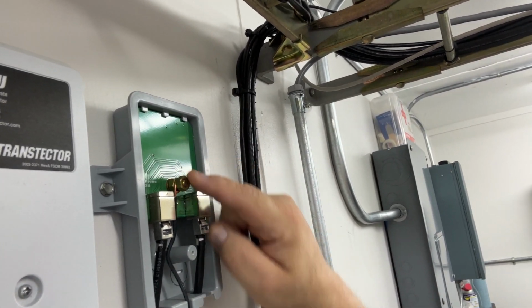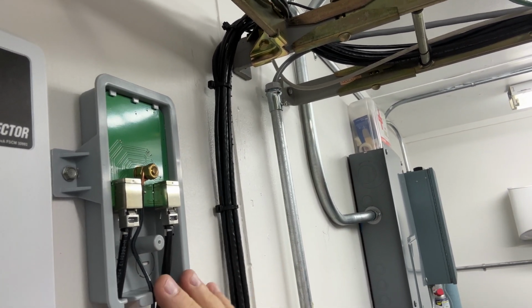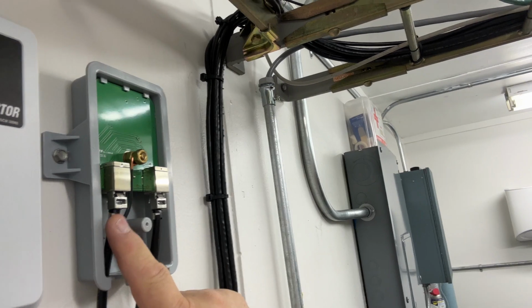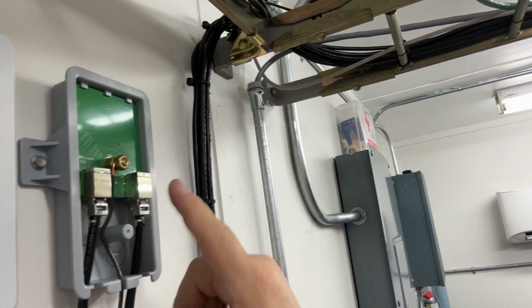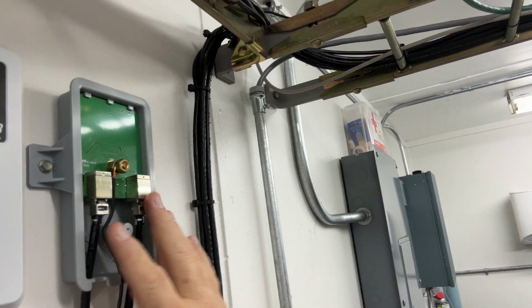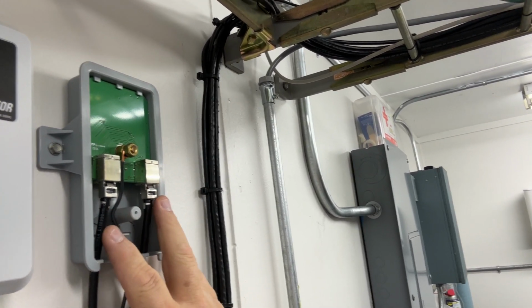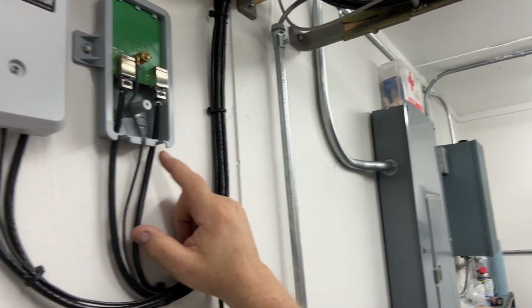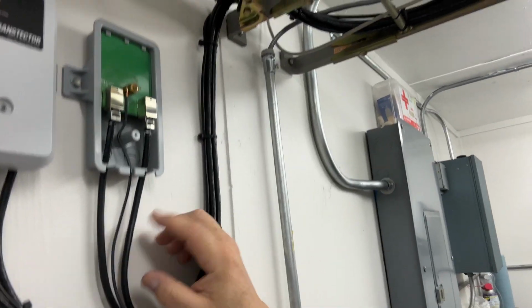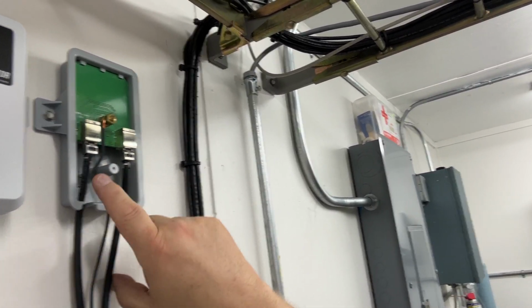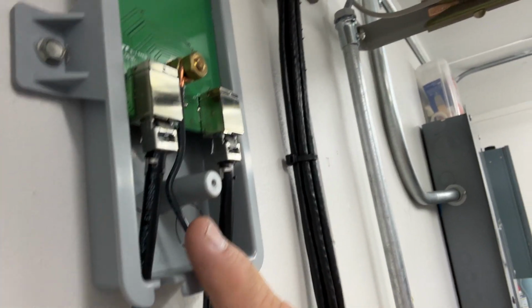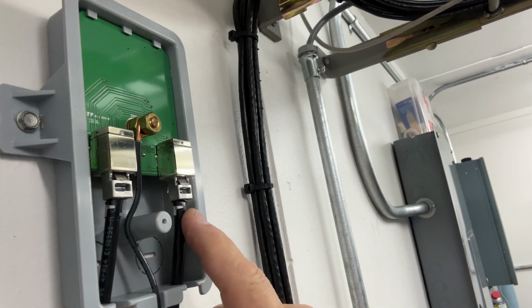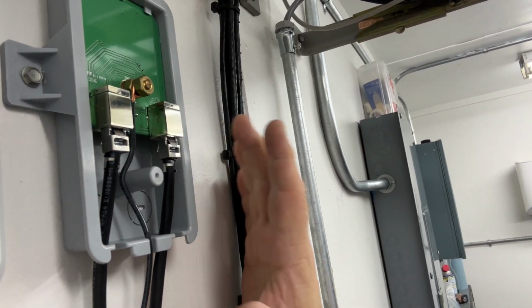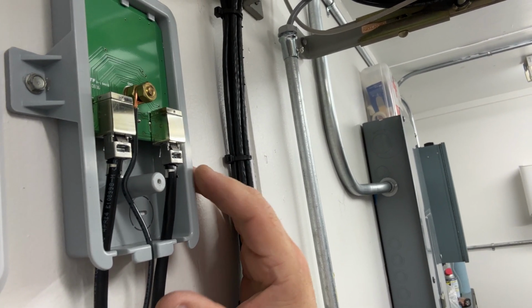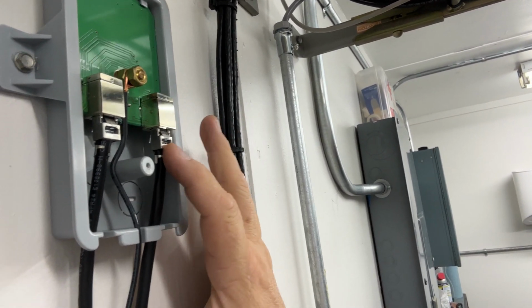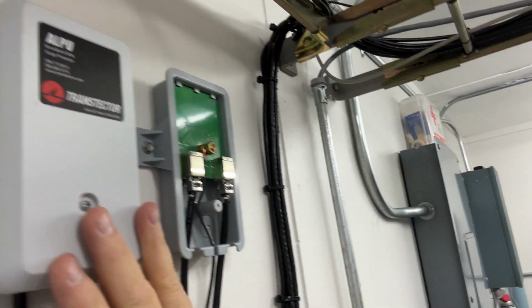And got the ground lug to go to our grounding bus here inside the building. You got your in, you got your out. It could be out, in, out. It doesn't matter which side you put these on. It's just flowing through gigabit speeds. But again, if it's going outside, we want to make sure that it's shielded, and this is shielded cable. In fact, you could see the shielded connectors on here. Let me get up a little closer so you can see that. Yep, some shielded connectors here so that all the way up the tower, we're not going to have a problem with a lightning strike or anything like that because it's grounded all the way from the top down to the bottom.